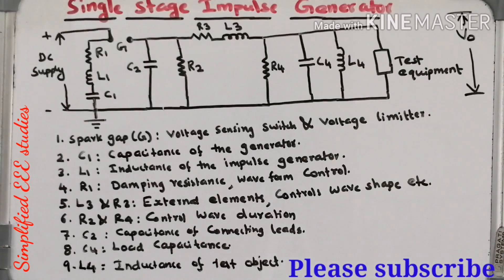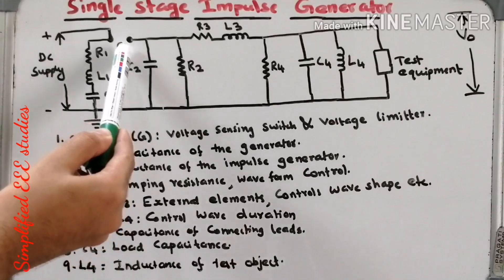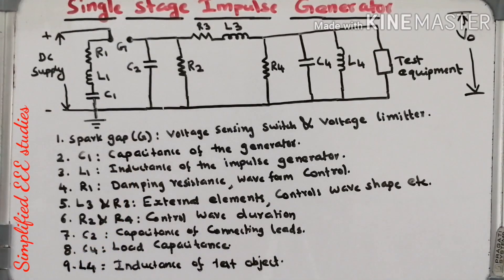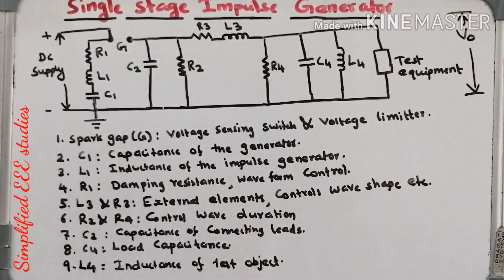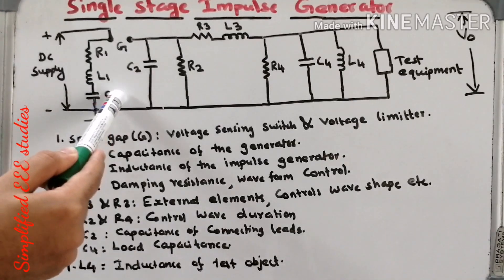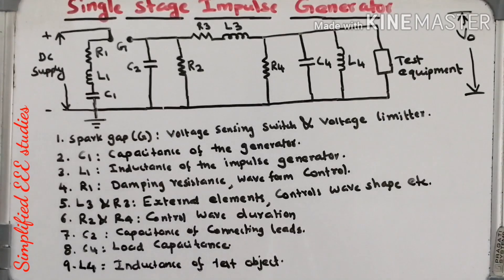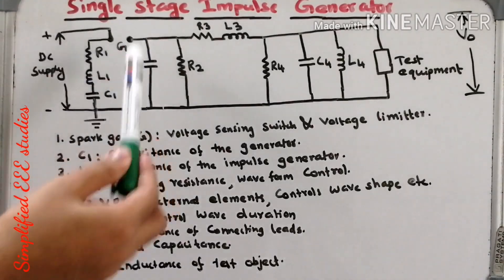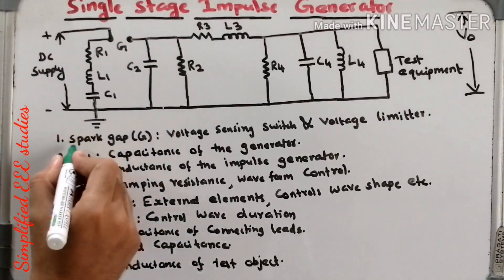Now let us familiarize with individual components. First and foremost, I would like to introduce the sphere gap. This is a sphere gap. The duty of sphere gap is that it is a voltage sensing switch. It acts as a switch and we can say it is a voltage limiter. It ensures how long the capacitor charges. Once capacitor C1 gets charged completely, the sphere gap G is going to conduct, then it provides a discharging path. That is the duty of the spark gap or sphere gap.